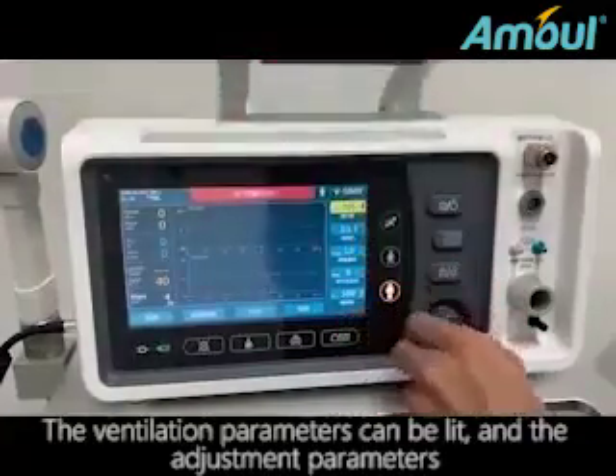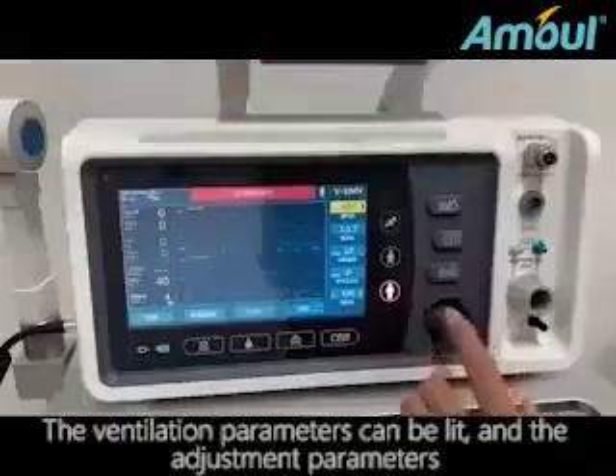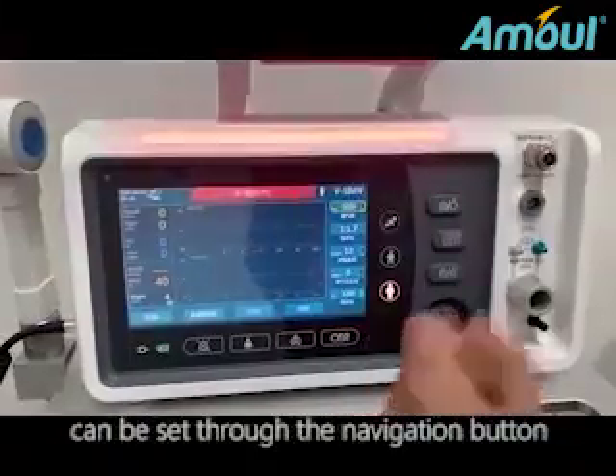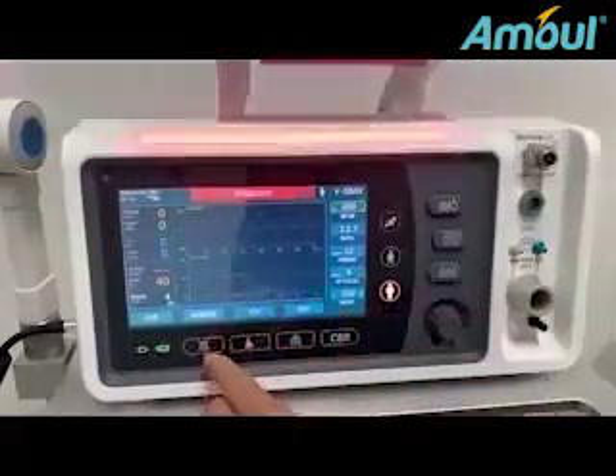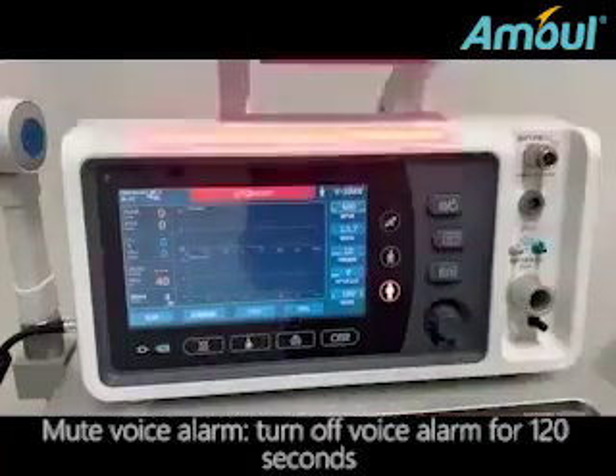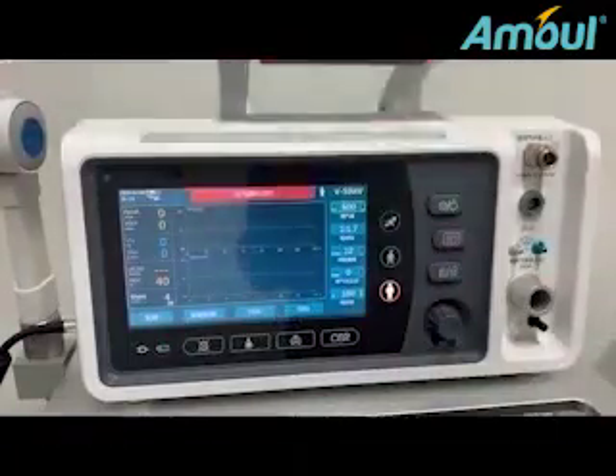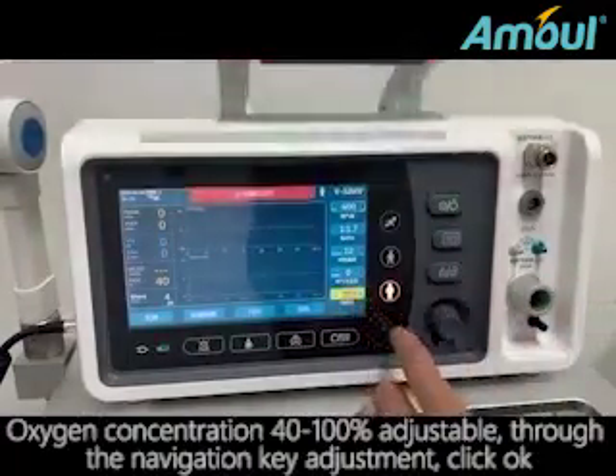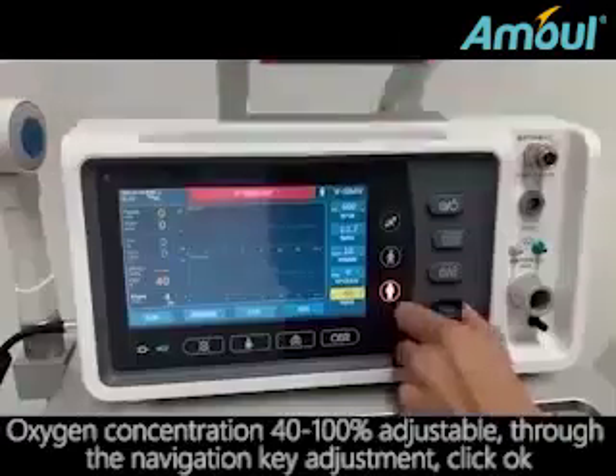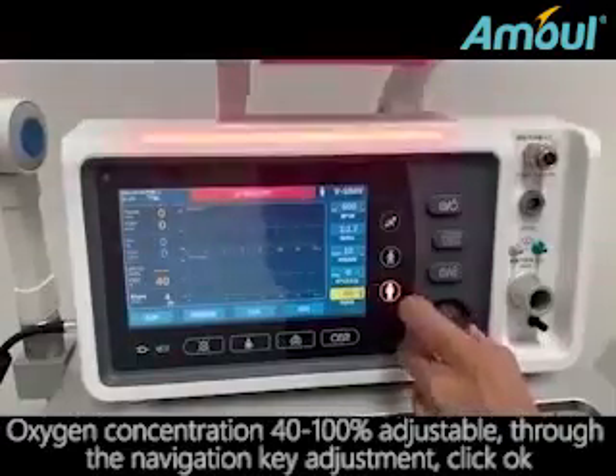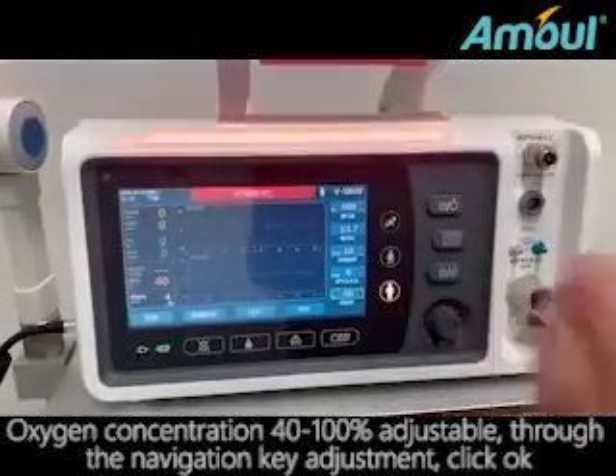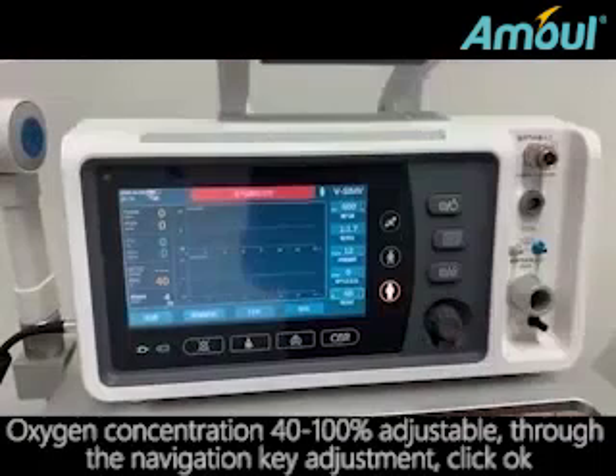The ventilation parameters can be lit, and the parameters can be set through the navigation button. Mute voice alarm: turn off voice alarm for 120 seconds. Oxygen concentration, 40 to 100%, adjustable through the navigation key adjustment. Click OK.